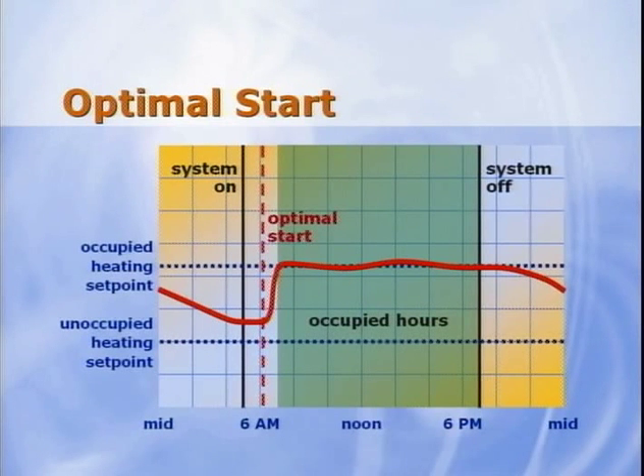This optimal starting time is determined using the difference between the actual zone temperature and the occupied set point, and comparing this difference with the historical performance of how quickly the zone is able to warm up or cool down. This strategy reduces the number of system cooling and heating hours and saves energy by avoiding the need to maintain the indoor temperature at the occupied set point, even though the building is still unoccupied.